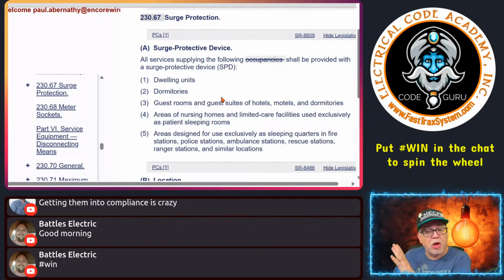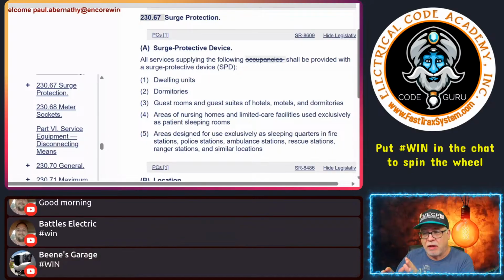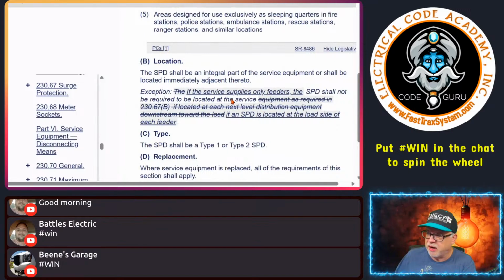I thought it was better placed to make sure that, for example, in multifamily buildings we have surge protection, because there's a high probability that the tenants can't get to the service area, which is probably down in the locked room for the multifamily building. And because of the size down there, there's a high probability that there isn't any SPD protection at all, because this applies to dwelling units, not to the multifamily dwelling itself. So again, this could be confusing, right? Now, here is the location requirement. The SPD shall be an integral part of the service equipment or shall be located immediately adjacent to it. Immediately adjacent, folks, means right beside it. People say, well, I want a distance on that.